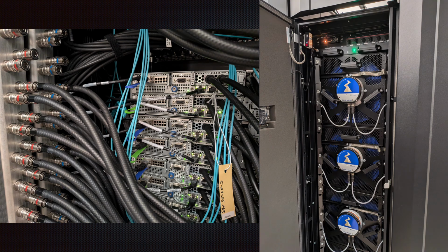We also have liquid cooling. These are glycol systems that run into the H100 servers, and there's a heat exchanger that sends this heat into the university's chiller loop. So we actually have a central heat sink that we're able to deliver some heat into, and we also have liquid-to-air heat exchangers, like these fans on the right, that transfer some of that hot water from the servers into the air.